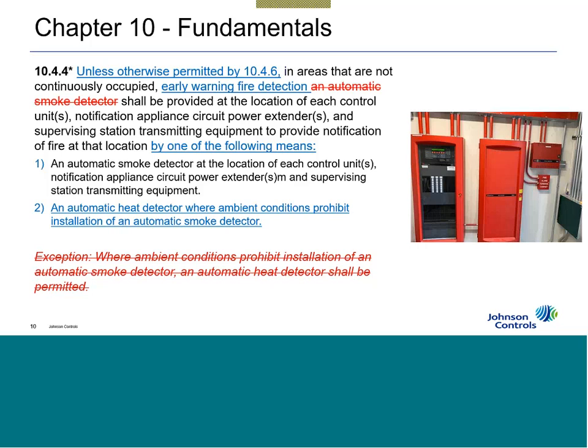to help with this. So several cycles ago, they enacted the requirement of a smoke detector to be installed above the fire alarm control unit. Further to that, because we want to do what NFPA calls signal preservation, we want to make sure the signal gets out to the first responders and to the people of the building, the smoke detector needs to be above the control unit, the notification appliance extender panel, NAC panel, booster panel, 4009, whatever you want to call it, and your supervising station transmitting equipment, your DACT, your IP communicator, cell communicator, what have you.